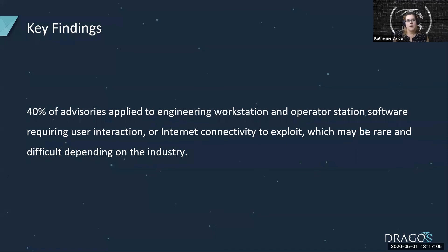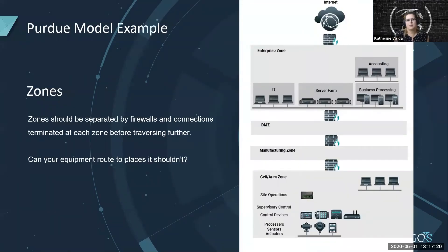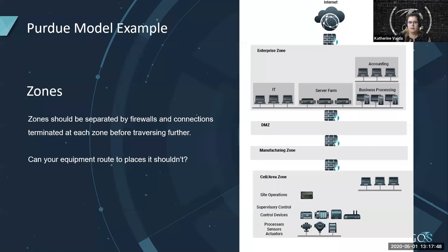40% of advisories applied to engineering workstations and operator station software requiring user interaction or internet connectivity to exploit, which may be rare depending on the industry. Zones should be separated by firewalls and connections terminated at each zone before traversing into the next one — meaning when your connection traverses through one zone, it should be terminated and reestablished, never crossing more than one at a time. Your engineering workstation or operator workstation software should not have connectivity to the internet, or at least not directly. It should be filtered through a firewall or proxy, keeping in mind that malware could be proxy aware. Update servers can live inside the DMZ, pulling down a trusted copy instead of having your systems reach directly out to the internet.